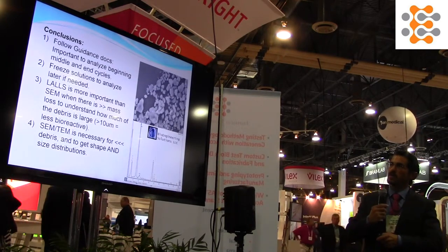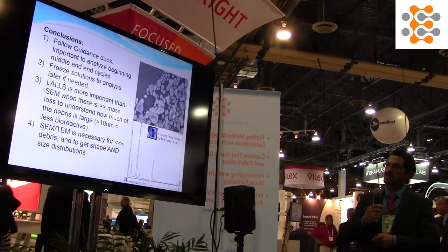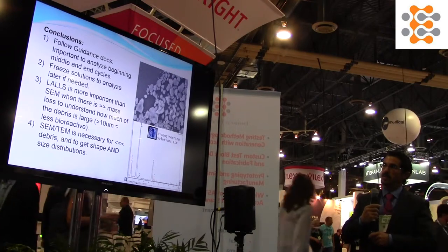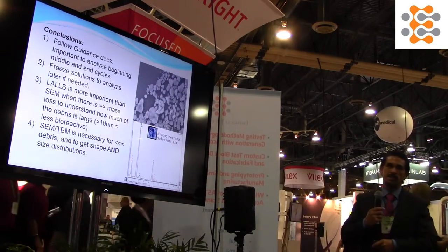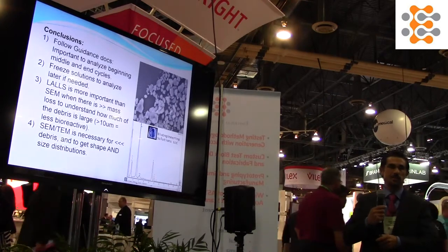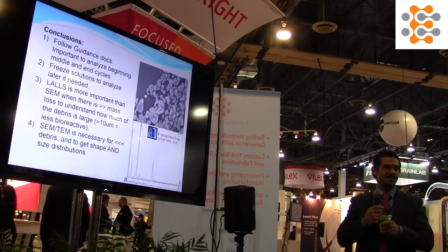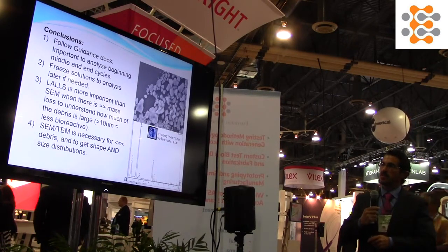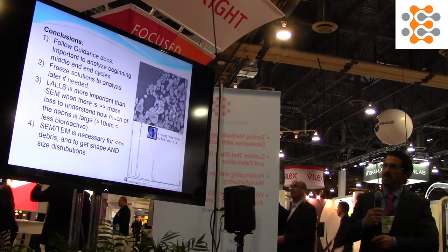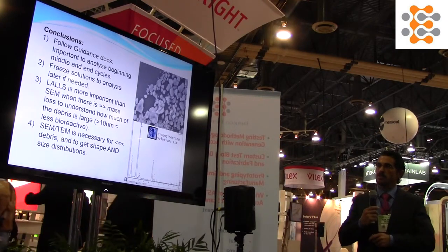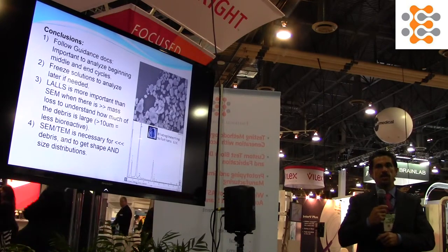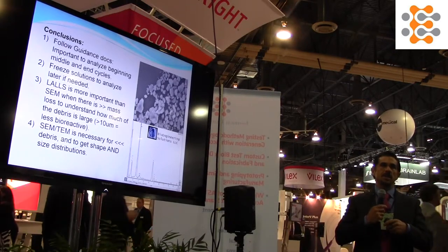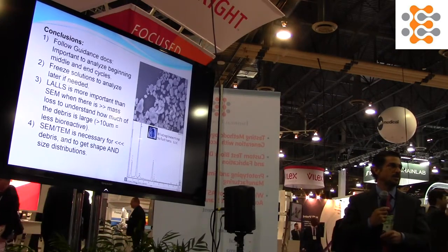Our conclusions are to follow guidance documents. Freeze solutions just in case you don't want to do particle analysis now but want to do them later — that will prevent metal debris from being digested by bacteria over the long term and turning into some sort of horrible soup. LALLS is more important than SEM when there is a lot of mass — a lot of powder — to understand how much of the debris is large. If there is a lot of large debris, that debris is not going to be as much in number, the dose goes way down, and the concerns for its biologic reactivity go down.